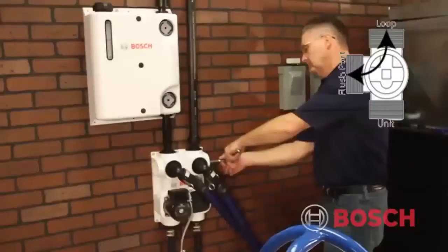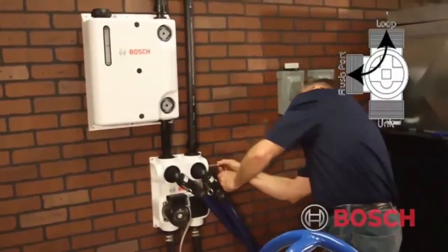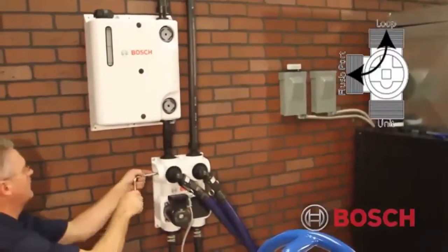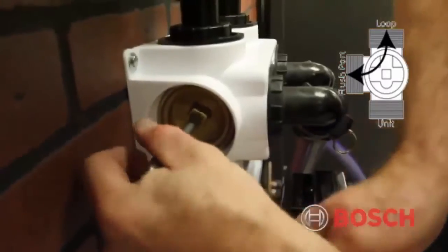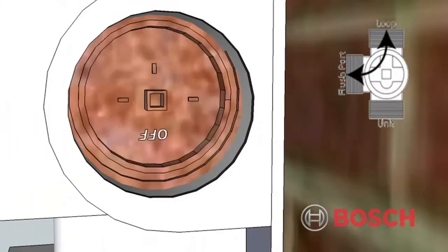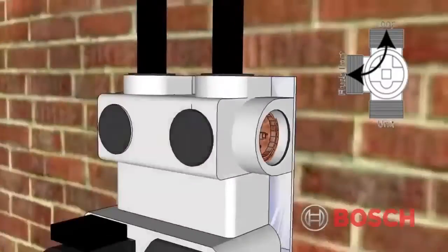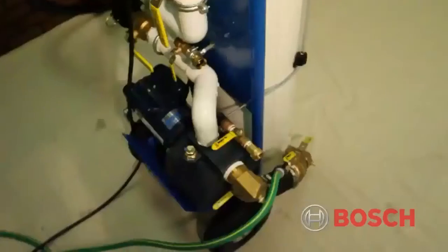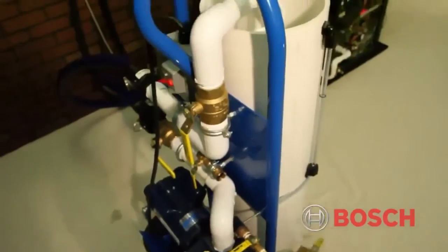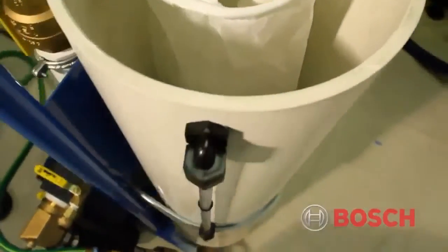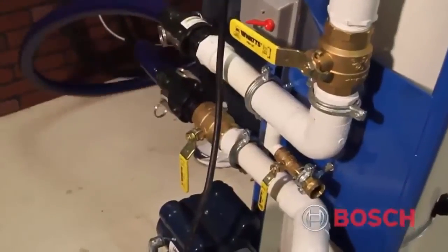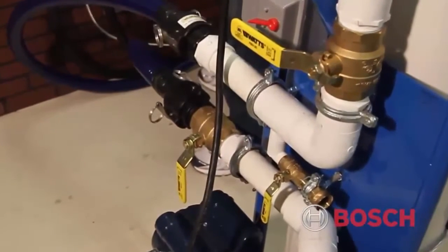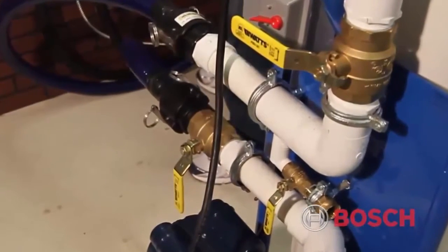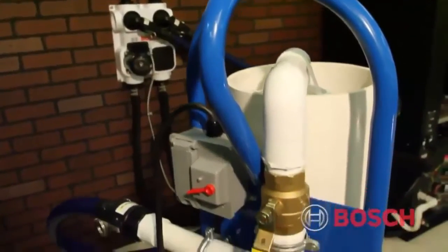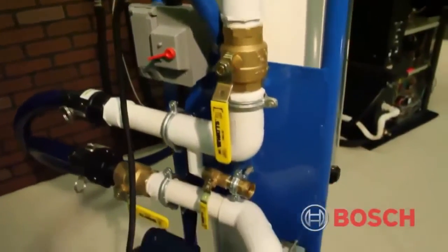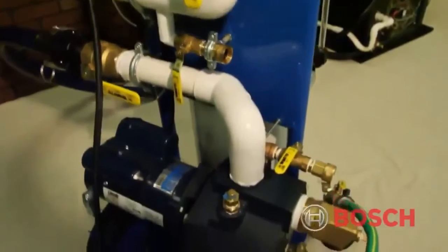Next, rotate the flow center three-way valves so that the off marking is set to the 6 o'clock position, thereby isolating the flow center and the heat pump from the ground loop. Now we need to verify our flush cart is set up properly. Verify the screen filter inside the reservoir is strapped to the PVC return pipe. At this time, all ball valves on the flush cart should be set in the off position. Connect the 20-foot flush cart power cord to a grounded 120 volt 15 amp circuit.